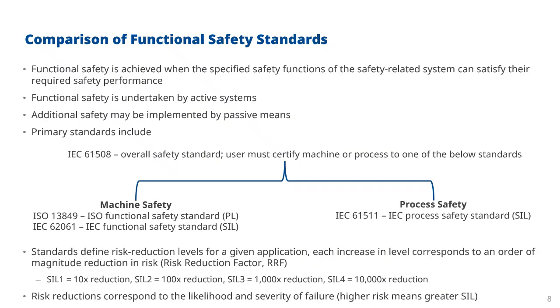Let's do a brief comparison of functional safety standards. Functional safety is achieved when the safety functions of a safety related system can satisfy their required safety performance. So functional safety is normally undertaken by active systems, but as we've seen before, you can also have additional safety that can be implemented by passive means. So the primary standard is IEC 61508. This is the overall standard, but this can't actually be implemented. You have to use one of these other underlying standards. So typically the vendor would certify their hardware to IEC 61508, but the user has to certify their machine or process to one of these other standards.